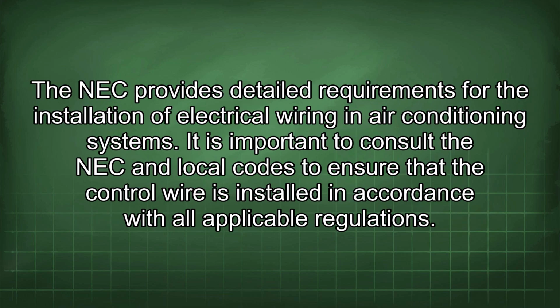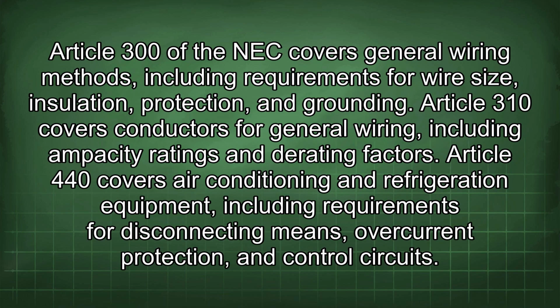The NEC provides detailed requirements for the installation of electrical wiring in air conditioning systems. It is important to consult the NEC and local codes to ensure that the control wire is installed in accordance with all applicable regulations. Article 300 of the NEC covers general wiring methods, including requirements for wire size, insulation, protection, and grounding. Article 310 covers conductors for general wiring, including ampacity ratings and derating factors. Article 440 covers air conditioning and refrigeration equipment, including requirements for disconnecting means, overcurrent protection, and control circuits.